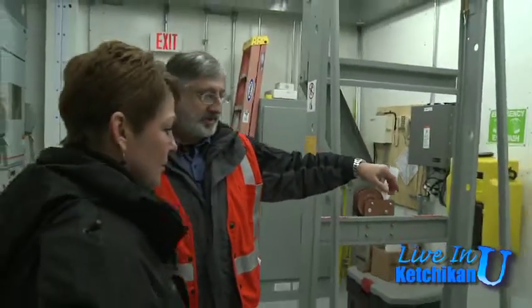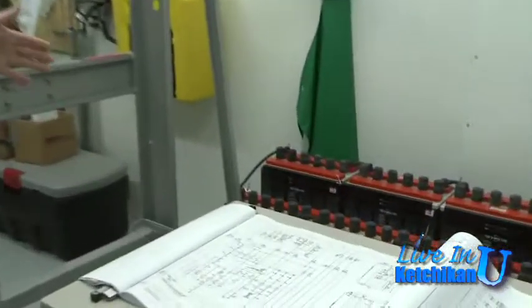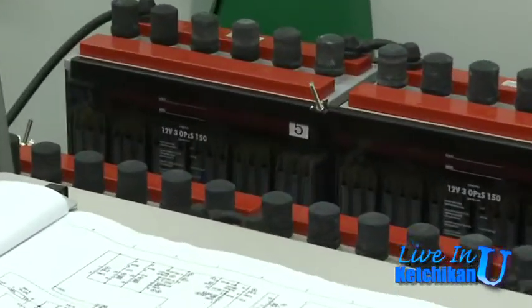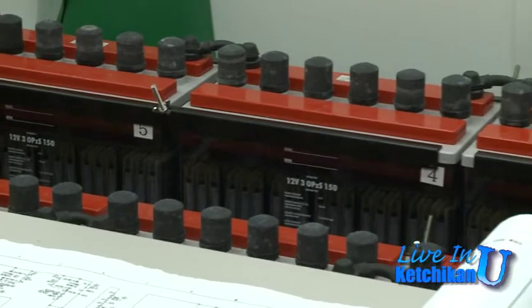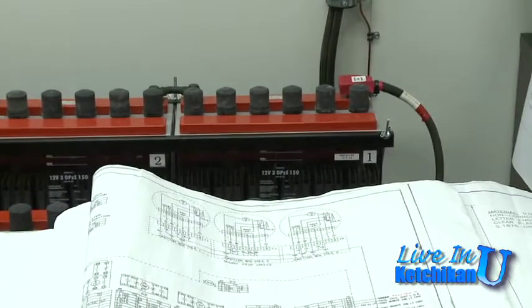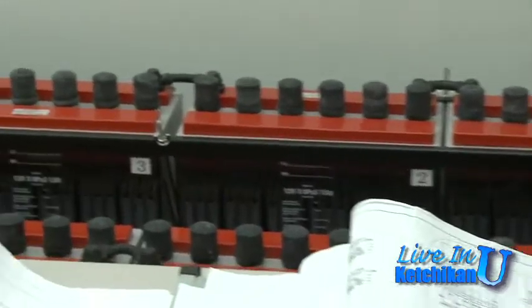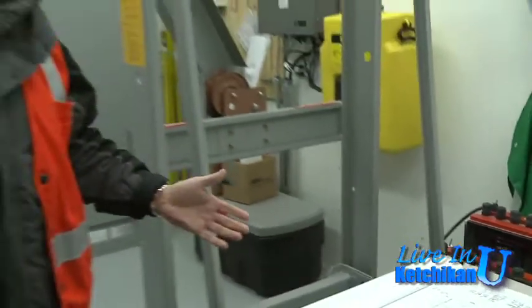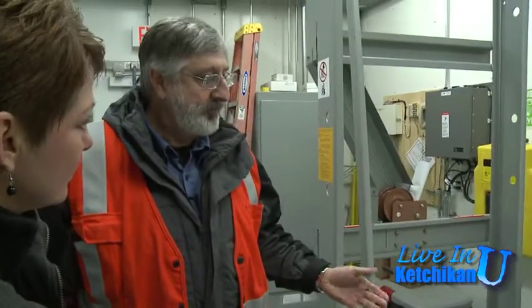You notice the rack of batteries here. Typical of substations, all the devices operate on DC, not AC voltage, and it's all 120 or 130 volts DC. The reason for that is if there's no power at all in a substation, the batteries are here to open and close the devices to bring power in.